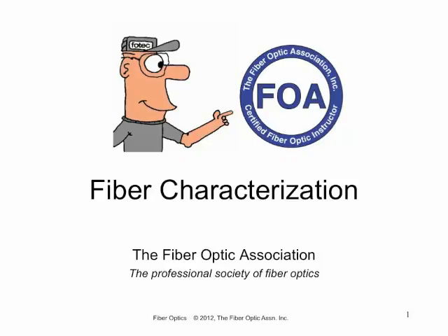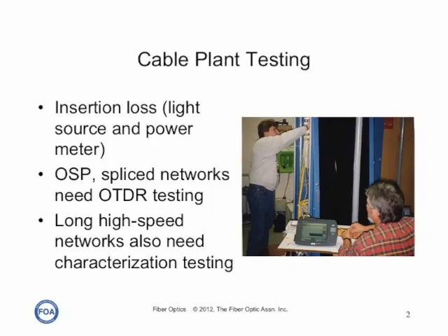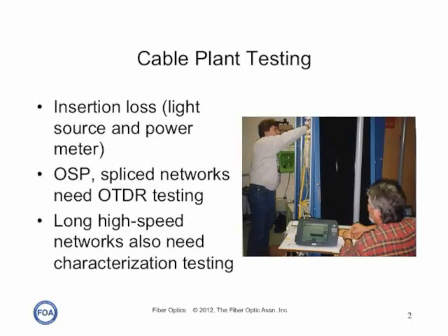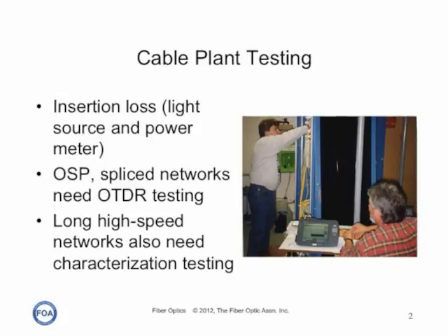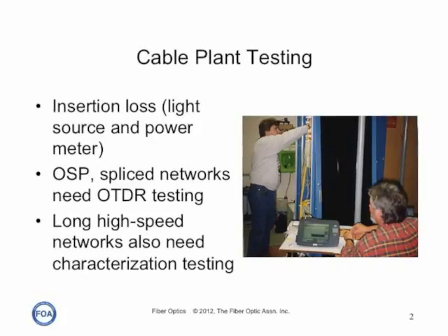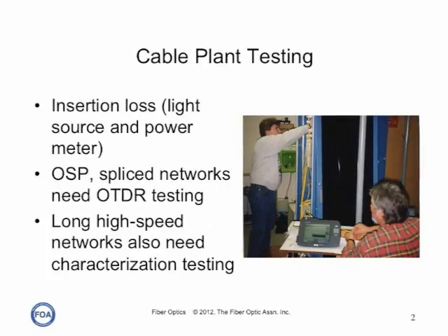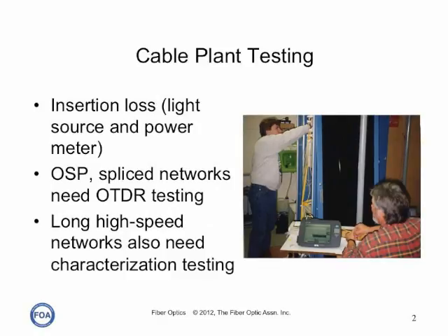We're going to look at the characterization of fiber that's already installed, particularly in long haul cable plants that often operate with wavelength division multiplexing and high bit rate systems. Every fiber optic cable plant should be tested by a light source and power meter, called an insertion loss test, because that test mimics the way the cable plant will be used by transmission systems, and provides the most reliable test data for ensuring the cable plant will work properly.